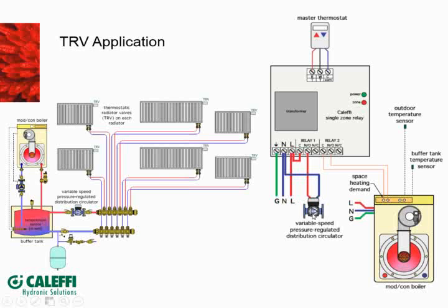And at the same time, we'll be firing up the variable speed pump so that the fluid is available as the TRVs start to modulate flow. The valves, there's fluid for that to flow through the panel radiators. So it's kind of a neat system that gets you one thermostat and gets you your individual room control, and it's without electricity really out on these TRVs.